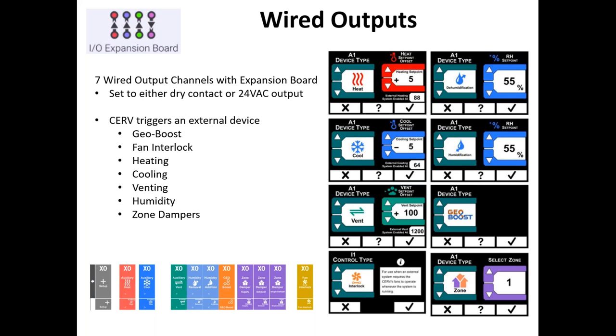Fan interlock: if you're connecting to a central air handler and you need the fan to run anytime the CERV is operating, fan interlock would be used for that purpose. And then probably the most common function is the zone dampers. The CERV controls the zone dampers directly through an output channel, opening and closing those dampers in this manner.